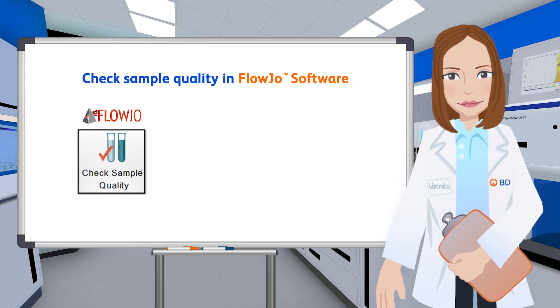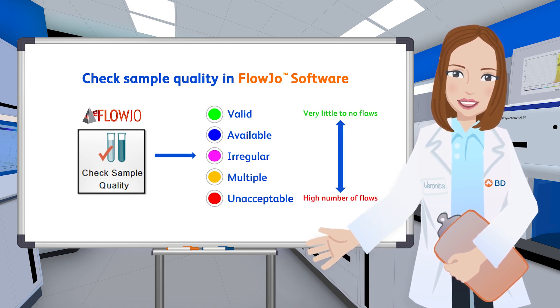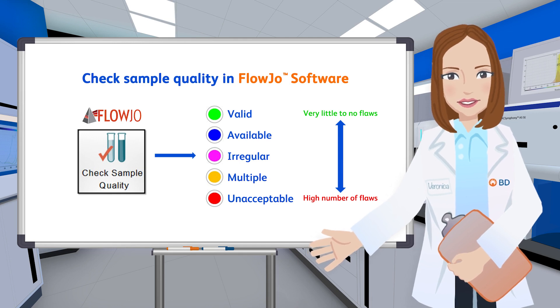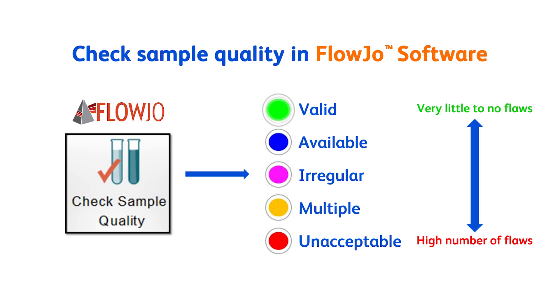Parameters compromising sample quality could be identified based on signal stability. Using this information, the check sample quality function will assign one of five badge colors to each of your samples. These colors denote the number of flaws, or variations from the median, found across all the parameters in your experiment. Green indicates a very smooth acquisition with little to no flaws detected. Blue indicates a low number of flaws, while magenta, yellow, and red reflect increasing numbers of flaws and thus lower sample quality.